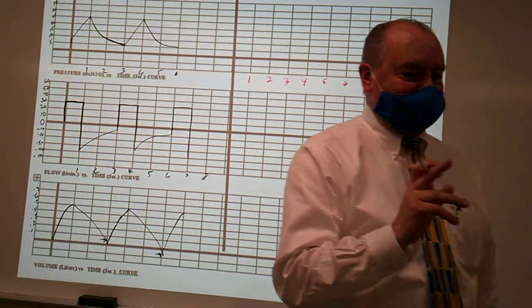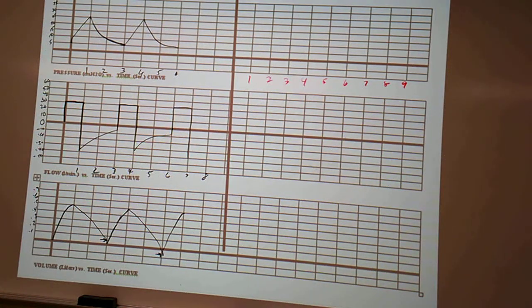Now on the test, it may appear one of two different ways, just to make it interesting. If it says set pressure, that's my pressure control level. If it says measured or observed, that's where it's actually going to.